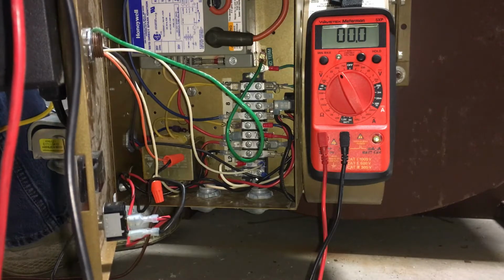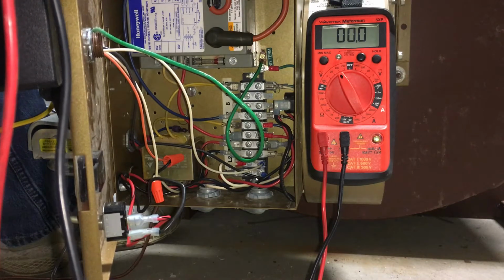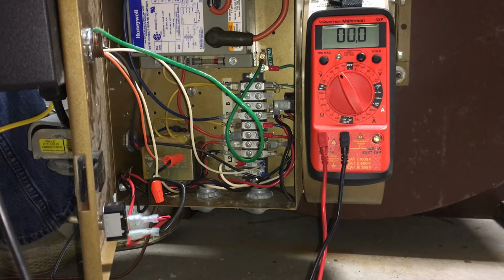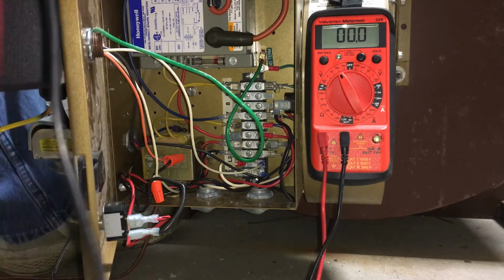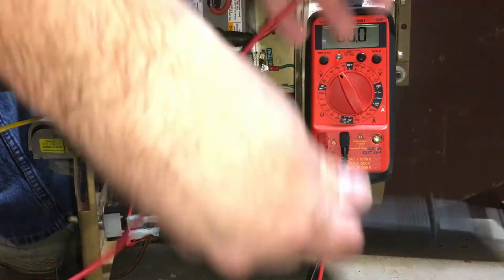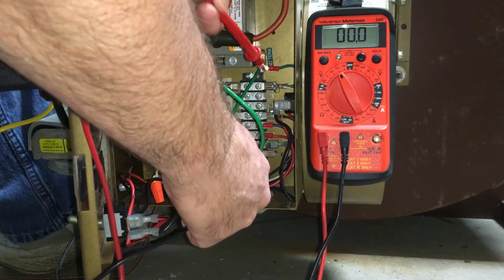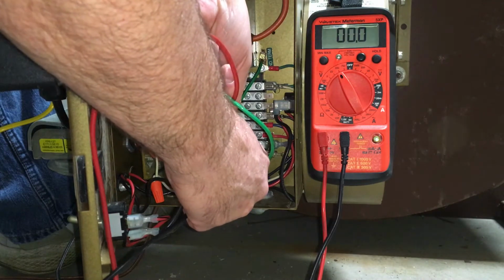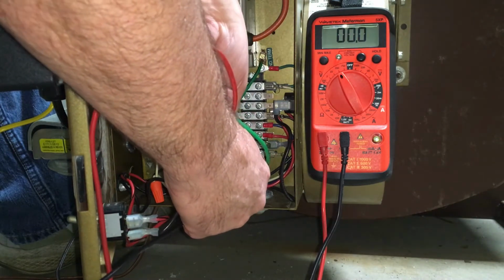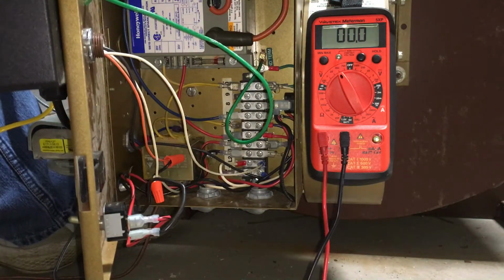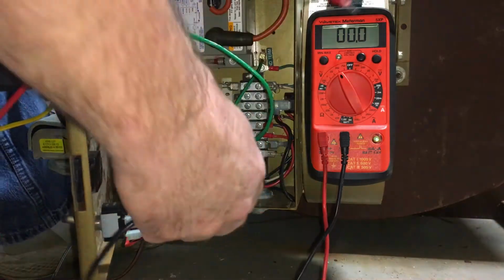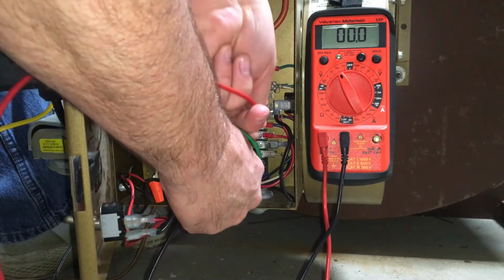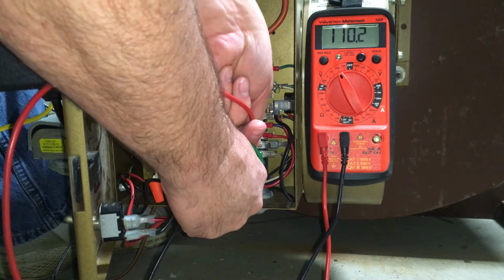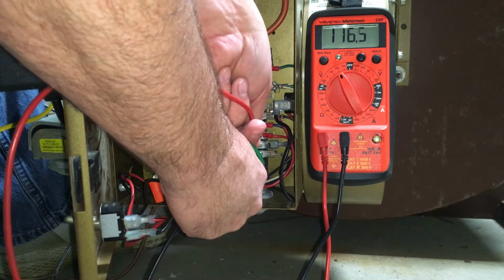That takes us to the next step under the motor will not run, and it asks to check for voltage across L2 and 3. That should be an optional on-off switch, which we do not have on here, but you can check through 2 and 3. And you see we don't have any voltage through it. All right, I'm going to verify whatever switch we have. I will test that again. Turn everything on. We are getting proper voltage through that as well.